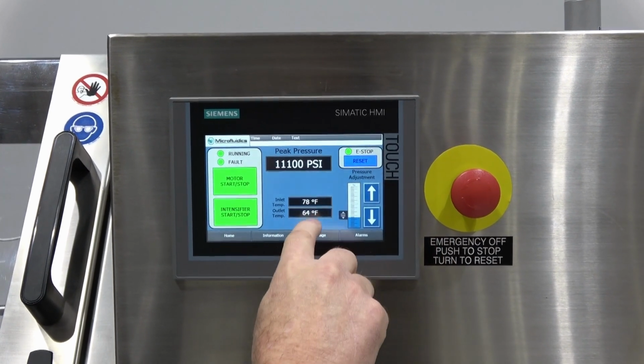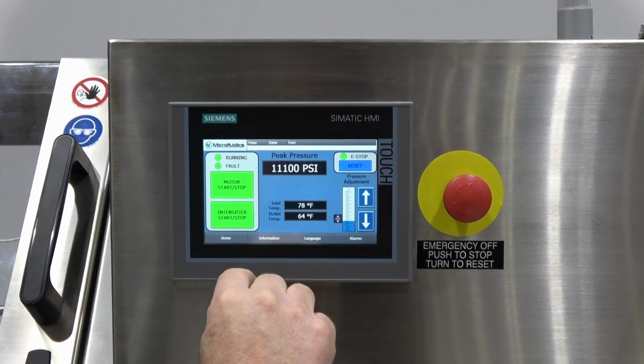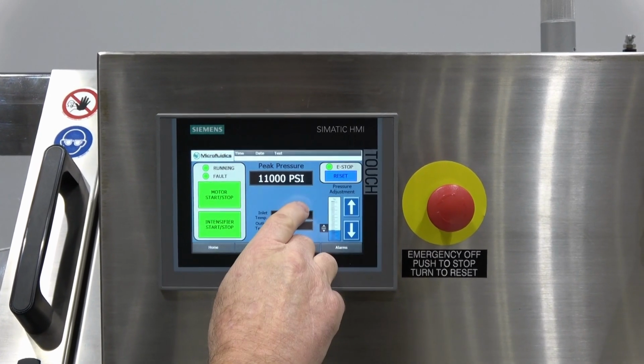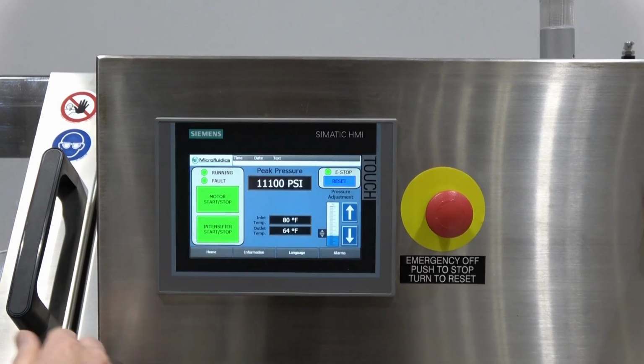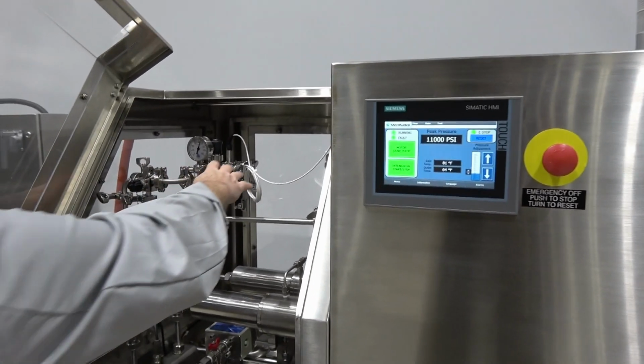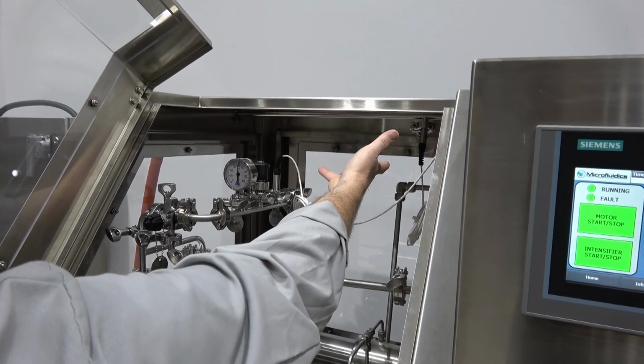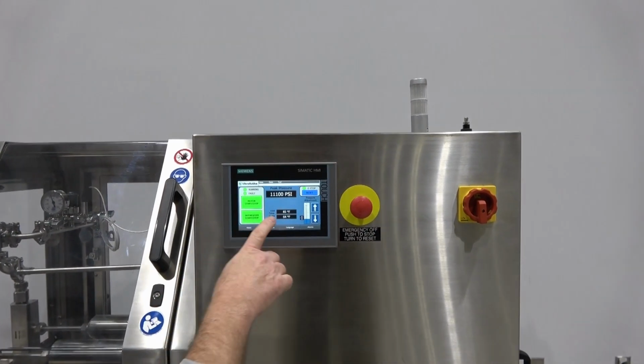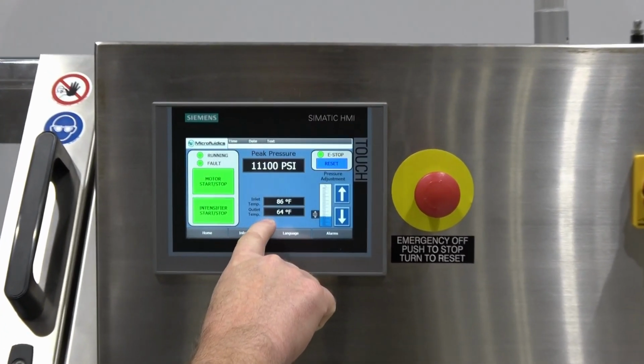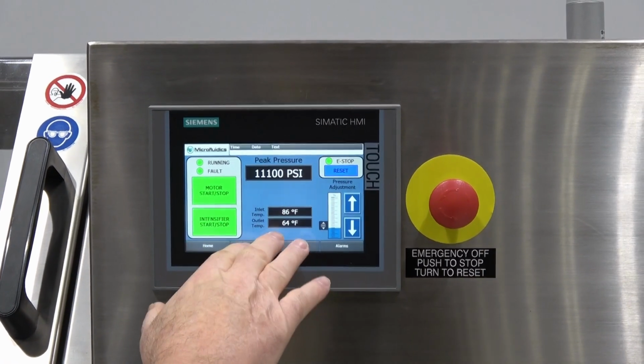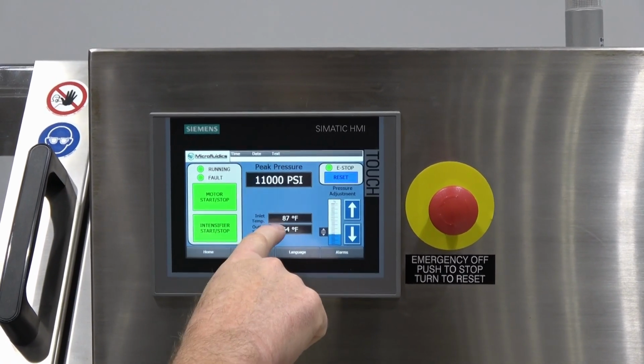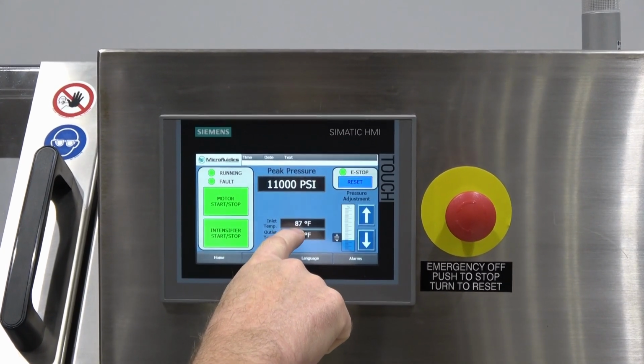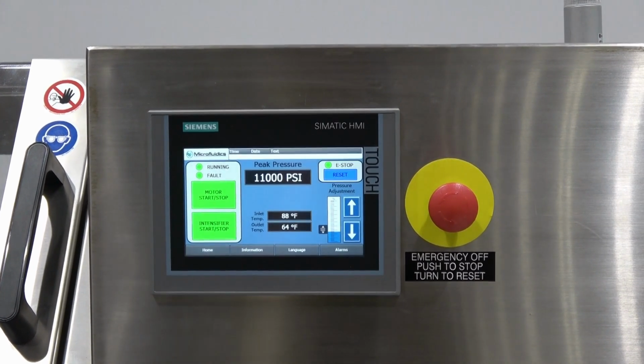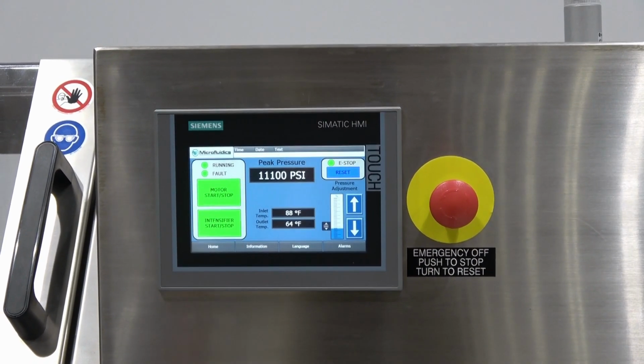And you can also see the temperatures here. Now I did notice one thing that I didn't fix yet. These temperatures are actually reversed. The inlet temperature over here, I'll just show you real quick. You got the inlet and you got the outlet. Well, these need to actually be reversed because they're reading backwards on the HMI here. The way I can tell is because the inlet temperature is over here, and it should be the one that's 64 degrees, because the outlet temperature should be the one that's climbing, because that's where all your heat's being generated, running it through the interaction chamber. So that's one thing I forgot.